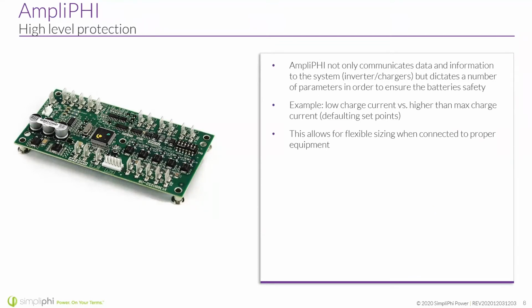You might see a lot of batteries that say, hey, we integrate with every single inverter on the market, we've already got all of them through our runnings. A lot of the time, those are really focused only on communicating data and information, not actually working out how the battery can drive the system and control different parts of it. The data and information side is fairly easy, but to have true communications with the system, we have to dictate a number of parameters and make changes to the system directly from what I'd call the brain of the system, the battery's BMS.